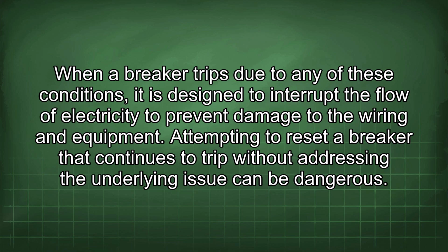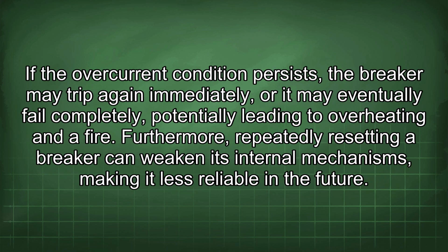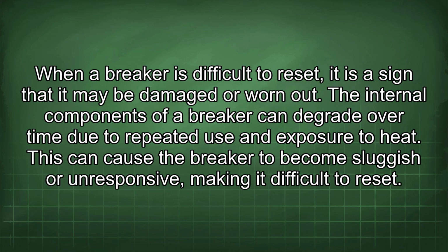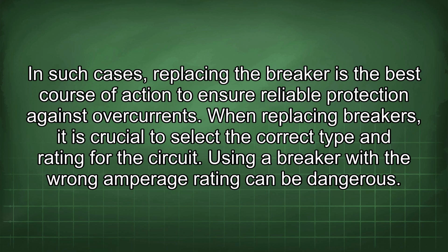Attempting to reset a breaker that continues to trip without addressing the underlying issue can be dangerous. If the overcurrent condition persists, the breaker may trip again immediately, or it may eventually fail completely, potentially leading to overheating and a fire. Furthermore, repeatedly resetting a breaker could weaken its internal mechanisms, making it less reliable in the future. When a breaker is difficult to reset, it is a sign that it may be damaged or worn out. The internal components of a breaker can degrade over time due to repeated use and exposure to heat. This can cause the breaker to become sluggish or unresponsive, making it difficult to reset. In such cases, replacing the breaker is the best course of action to ensure reliable protection against overcurrents.